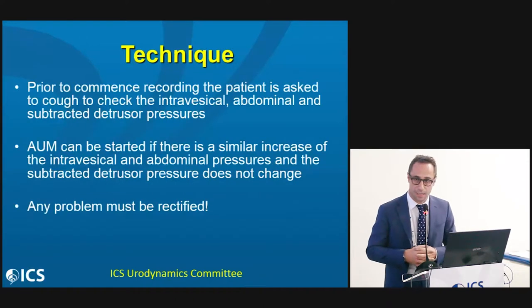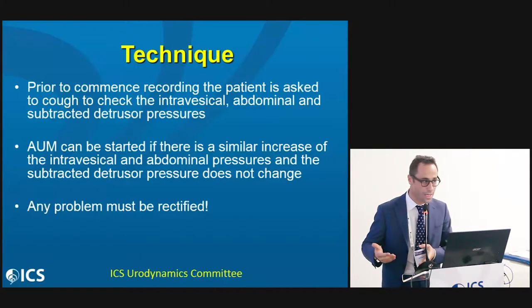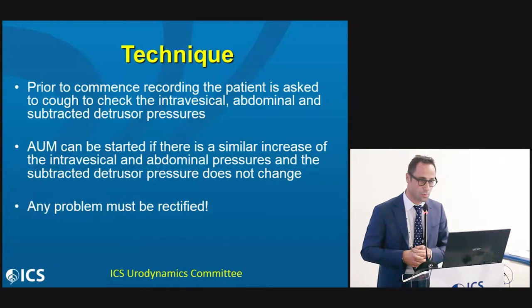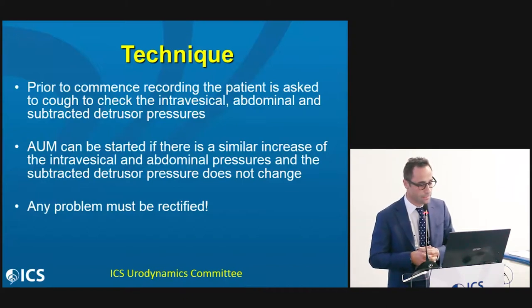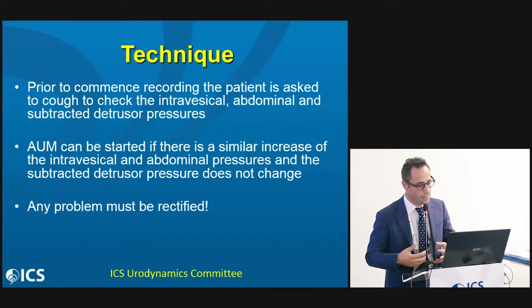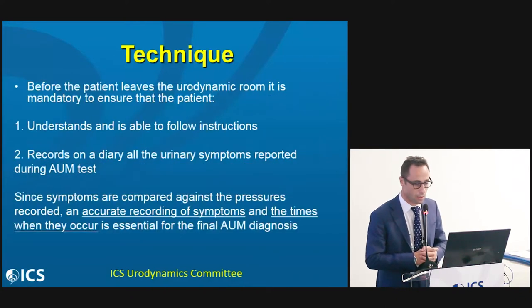After setting the zero, before starting pressure recording, we need to check whether the pressures we are recording are accurate and whether the subtraction is good. Therefore, we ask the patient to cough — the same way as during routine cystometry. If there is a similar increase in intravesical and abdominal pressure, then the subtraction is good and AUM can be started. If there is any problem, we must rectify it before starting recording.